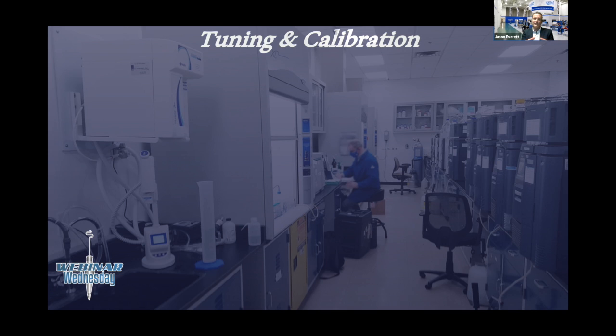And when I talk about calibration, we're talking about how the current that they give off needs to be calibrated to zero, just like we calibrate a set of calipers to the set point prior to measuring a piece of wood or something like that. We want to measure each one of these control valves, solenoids, IP converters, so that when pressure comes in and it's at a zero level, it's going to give off a 4 milliamp signal if it's a 4 to 20 milliamp communication device. And then when it's at the full 100% level, it's going to give off that 20 milliamp signal.